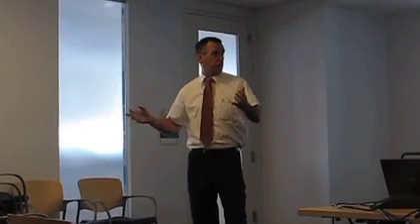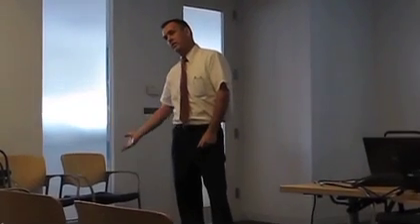What open transition is, if there's an outage, that obviously there's an outage and then the generator starts and you transfer over in a certain period of time. 10 seconds is a typical starting time. But when you're coming back and the utility is there and the generator is running, you can have an open transition, which means you shut the generator off and then go back to the utility. Or a closed transition is there's no outage. The generator and the utility come together and you don't see any type of blink in the lights when it's returning.